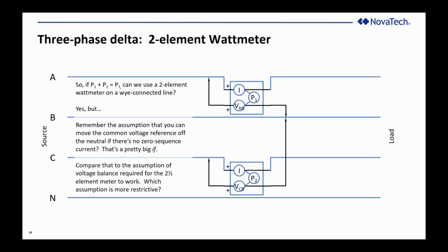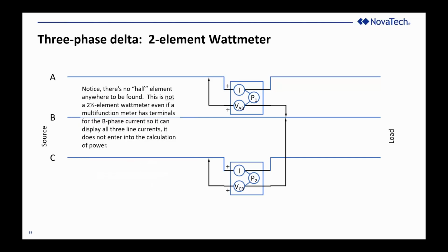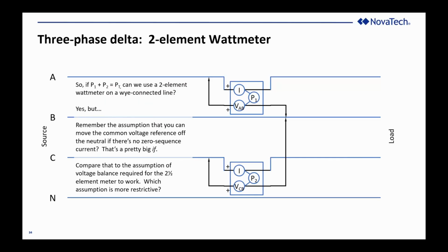The next question, I think, suggested by this is the presence of the neutral line. You see between these 2 slides, the presence of a neutral conductor doesn't really change so much the usefulness of a 2-element wattmeter. You could use a 2-element wattmeter if you had a neutral conductor, as long as there's no current flowing through it. So what I'm suggesting is, by comparison to a 2.5 element meter, where the underlying assumption is the voltage must be in balance for it to work, compared to a 2 wattmeter method, the 2-element meter, where the assumption is no zero sequence current, no neutral current, which of those presumptions of balance do you think is more restrictive? I think it's a lot easier, since the voltage is supplied and regulated.